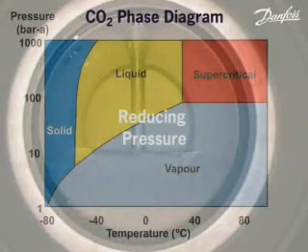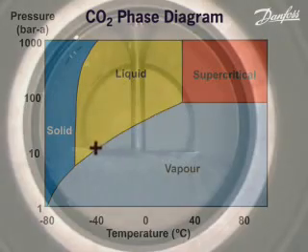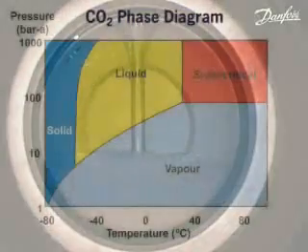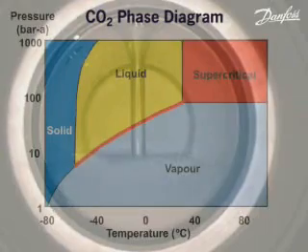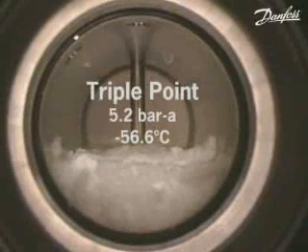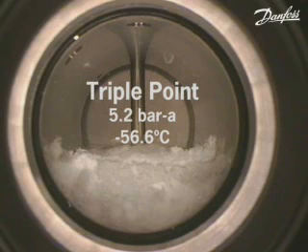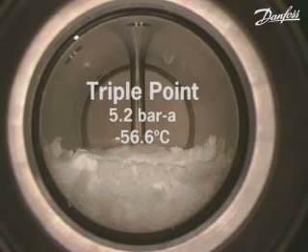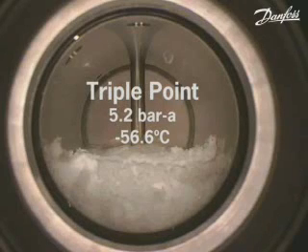The triple point is reached with further reduction in pressure and temperature. The system has now moved further down the vapour-liquid equilibrium line. Solid CO2 begins to form once a pressure of 5.2 bar absolute and a temperature of minus 56.6 degrees C has been reached. The triple point is the only pressure and temperature combination at which solid, liquid and vapour CO2 can exist simultaneously in equilibrium.